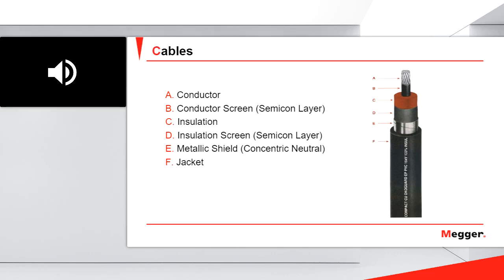Okay, talking about cable construction, what we are seeing in this slide is the typical one-phase cable. Of course, we can have different materials. For instance, we have a conductor. In this case, it is a conductor with aluminum wires. We could have copper wires, so it could be aluminum or copper. Then we have the semicon layer, the conductor screen. Next, we have the insulation of the cable. In this case, we have EPR insulation. The most common today is XLPE insulation, but in some countries we still have paper insulated cables.